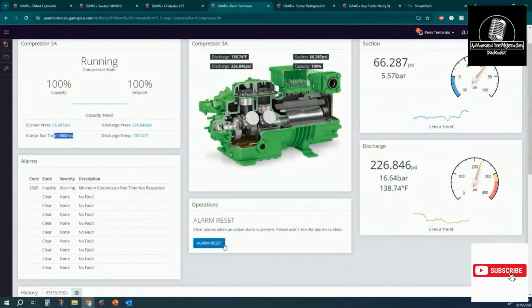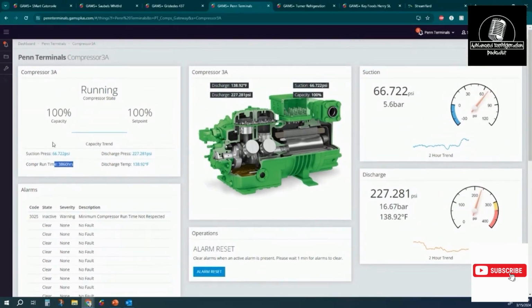If it was an alarm, we could hit alarm reset right from here. If we had the right credentials and properly troubleshot it, without going up on the roof of this plant in Philadelphia, we could reset it, and then the Bitzer can be off and running, and we can monitor it from here.